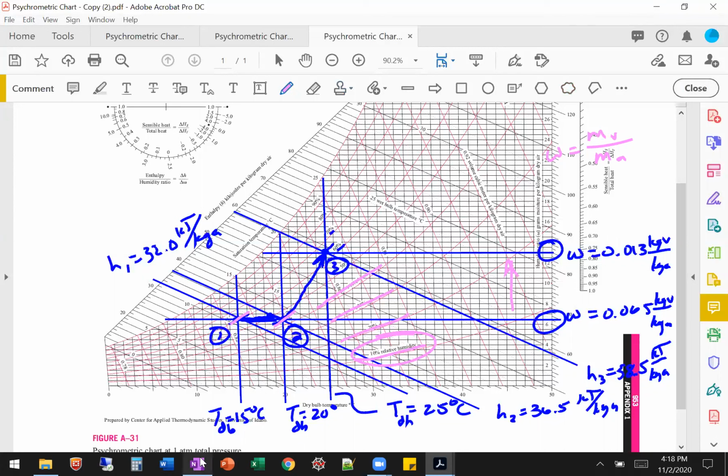Thanks. That makes sense. Yeah, so those stay the same. That's why specific humidity is the better quantity in the math part, the engineering part. But relative humidity matters because that's where we know what people like. In HVAC, people like around 40 to 60% relative humidity to feel comfortable.